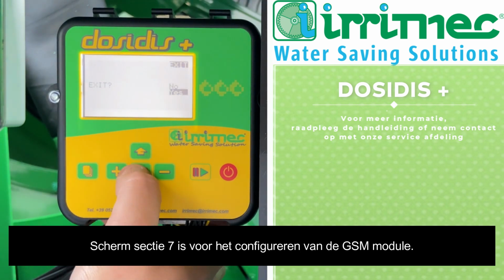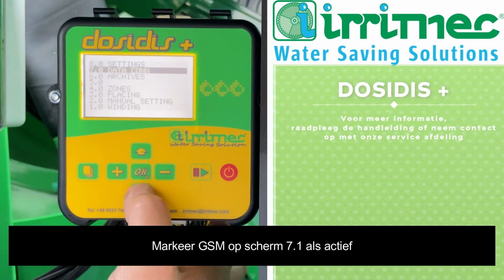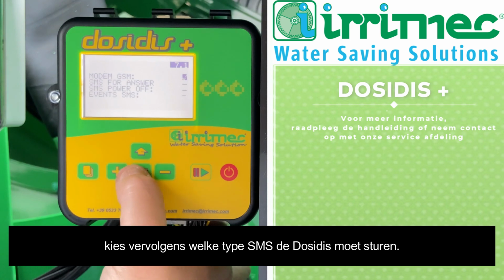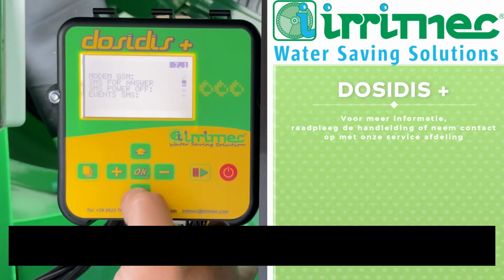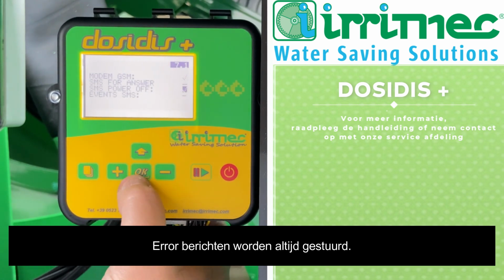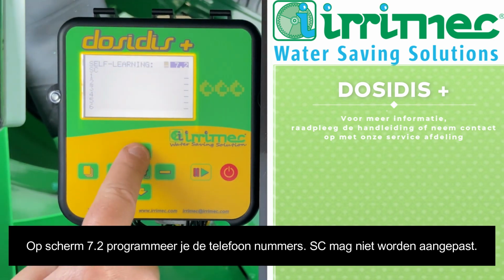Section 7 is for GSM and connection configuration. On screen 7.1, flag GSM as active. Then select what kind of SMS the Dosidis should send. Error SMS are always sent. On screen 7.2, program phone numbers. SC should not be modified.